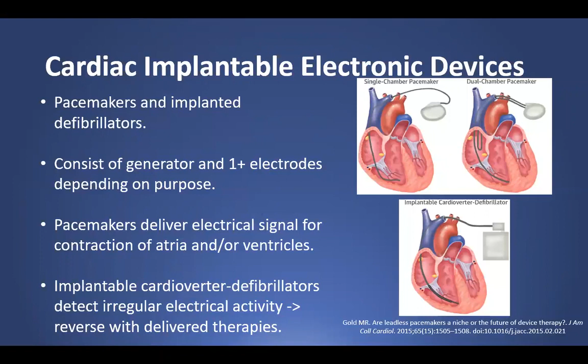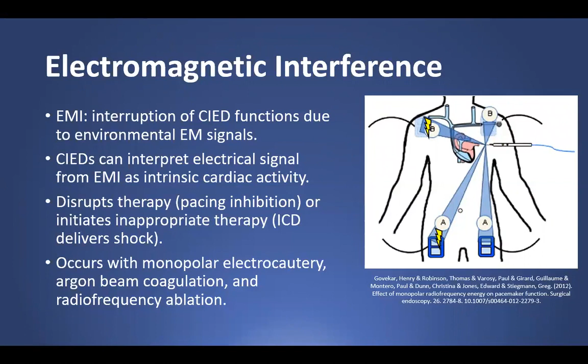This disruption can occur with electromagnetic interference, or EMI, due to the devices interpreting EMI as intrinsic cardiac activity. In the setting of pacemakers, this may cause the pacemaker to stop delivering therapy. In the setting of ICDs, this could lead to the device delivering an unnecessary shock. EMI can occur with any monopolar electrocautery, including argon beam coagulation, as well as radiofrequency ablation.